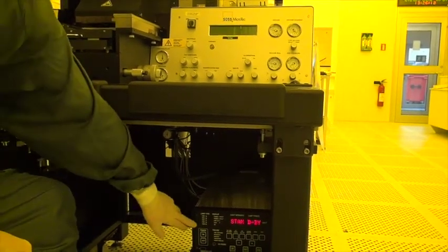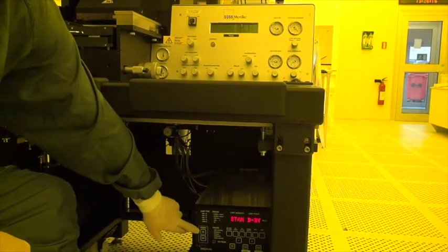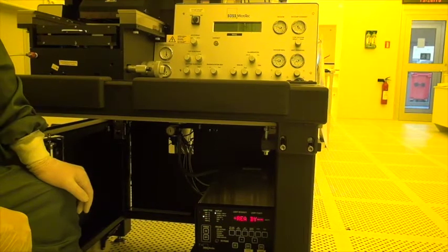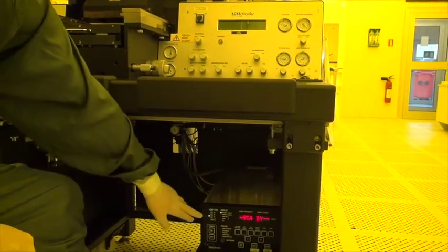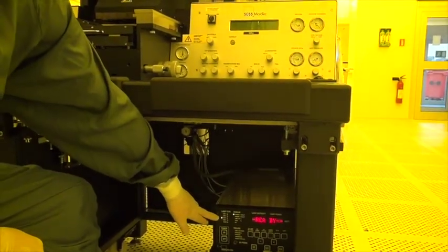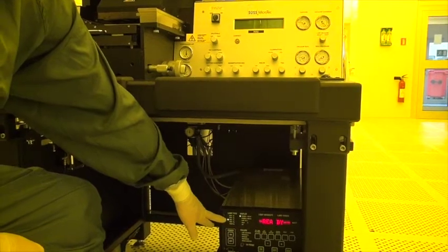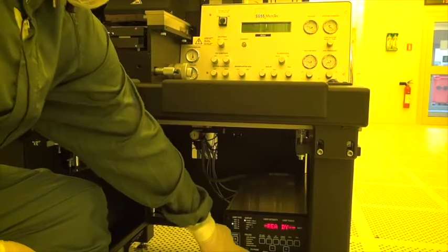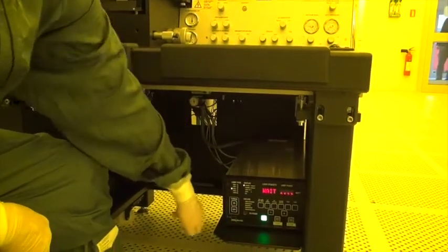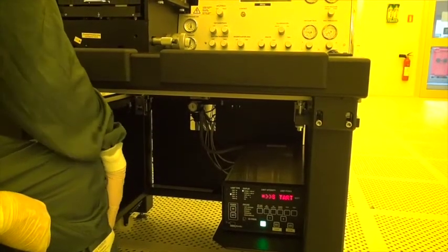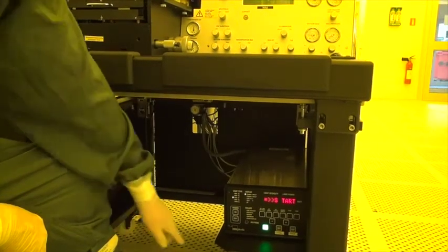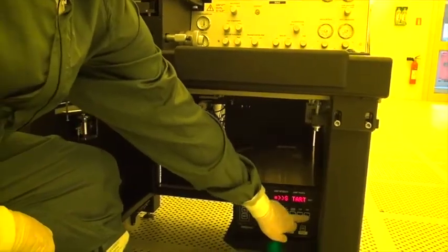Then on the power supply for the lamp we press on. We verify that the lamp is correct, 500 watt xenon. When it says ready we can press CP for constant power. And upon indicating start we can ignite the lamp by pressing start.